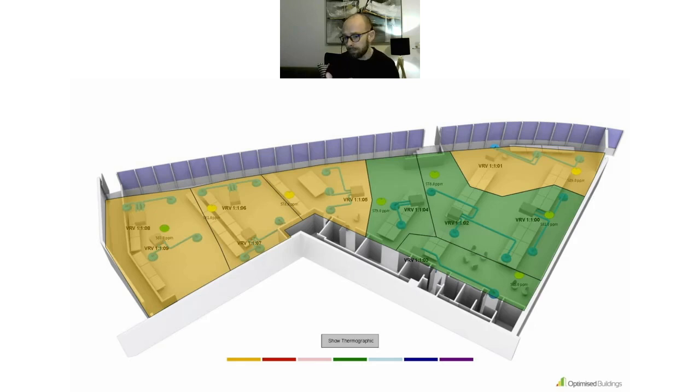And so, like I said, this project only went live a week ago, and we're already realizing, through the data that we're collecting from the sensors and the data that we're getting through the control from the Daikin, that we've identified that there are some zones that are struggling to heat. This space is actually river facing in Battersea, literally right on the river towpath there. So we get some strong winds and some cool breezes coming in there.